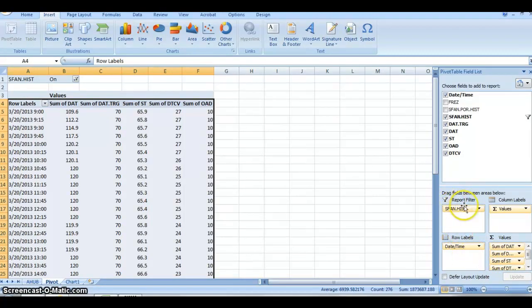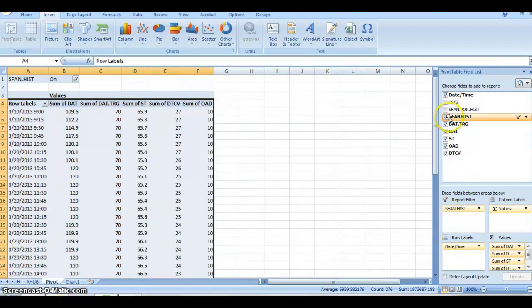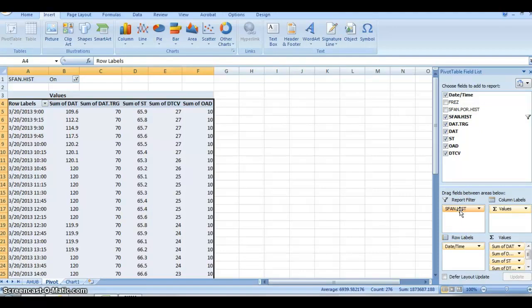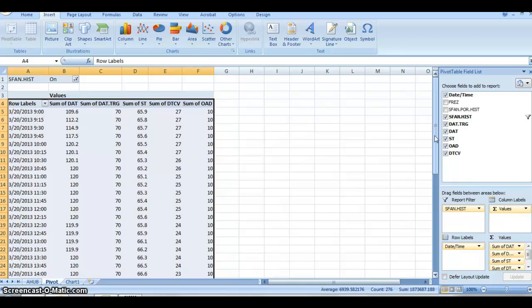We have a report filter option here. I put supply fan history in there because we only want to trend data when the supply fan is running. If the supply fan is not running, we're obviously not using our energy.